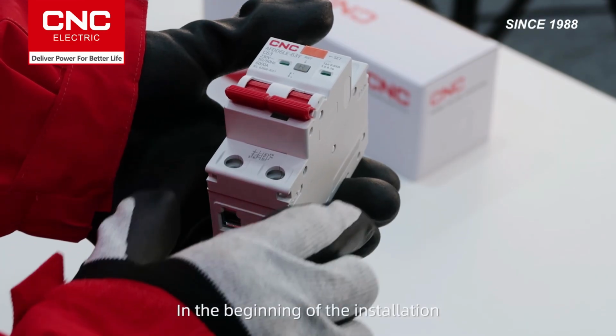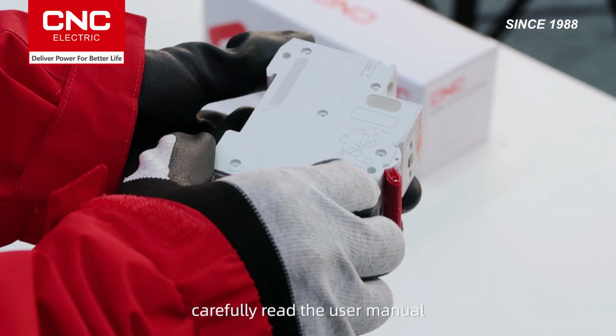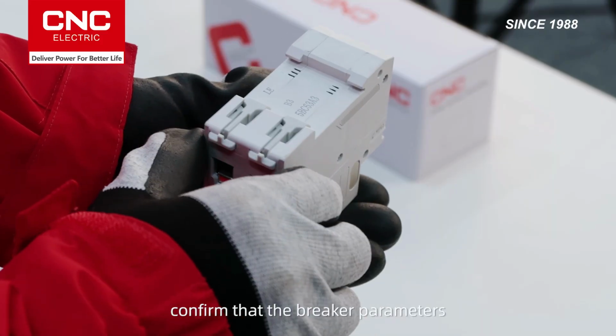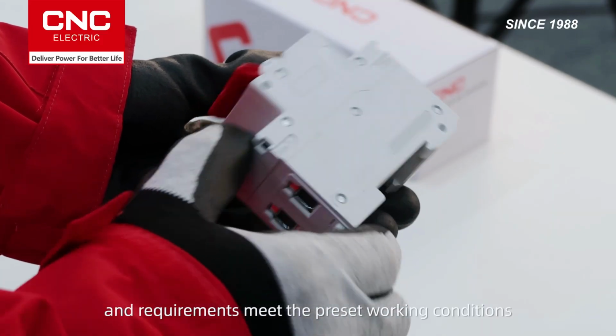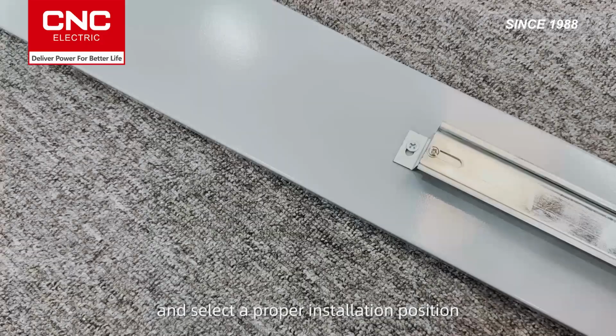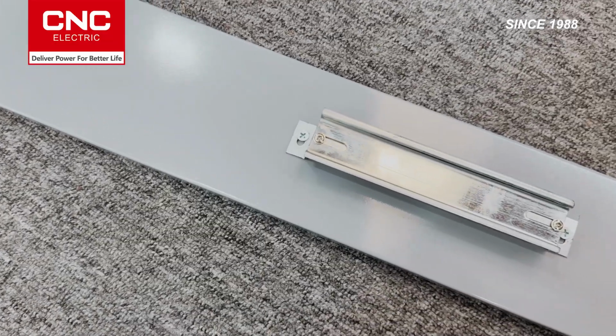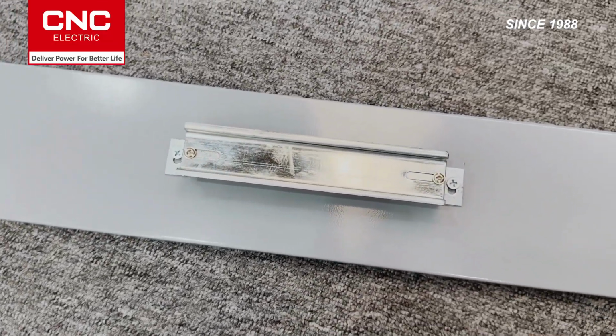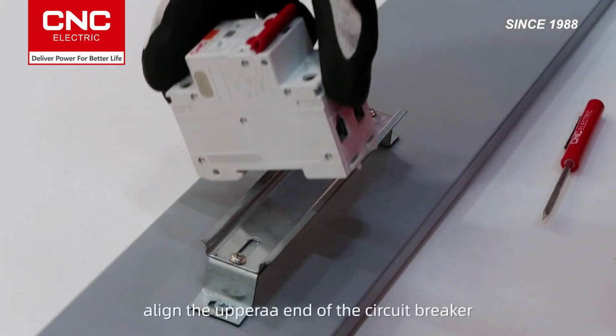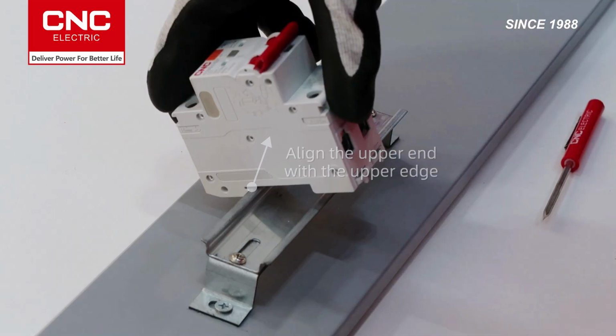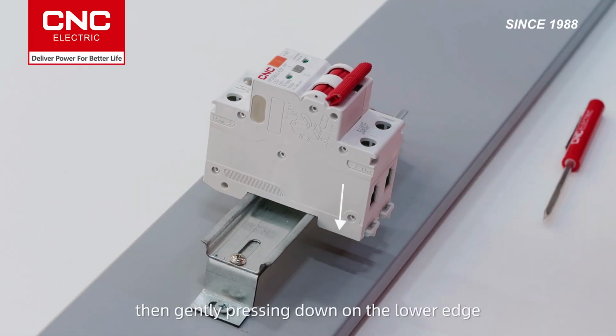In the beginning of the installation, carefully read the user manual, confirm that the breaker parameters and requirements meet the preset working conditions, and select a proper installation position. Installation tips. First, align the upper end of the circuit breaker with the upper edge of the DIN rail. Then gently press down on the lower edge.